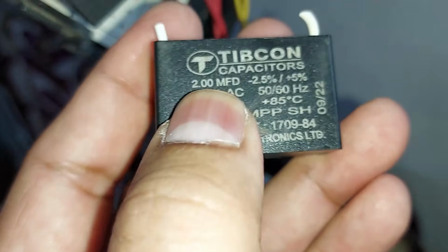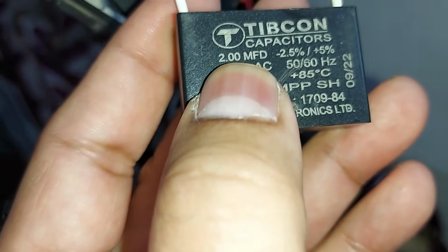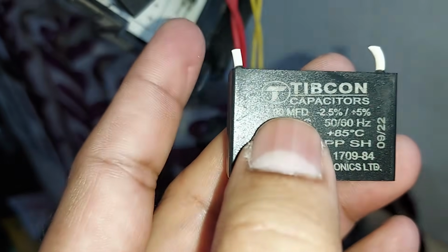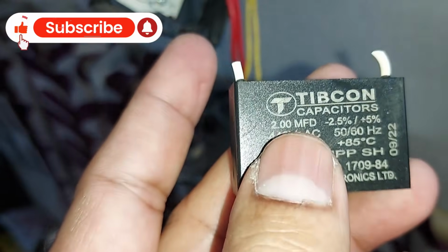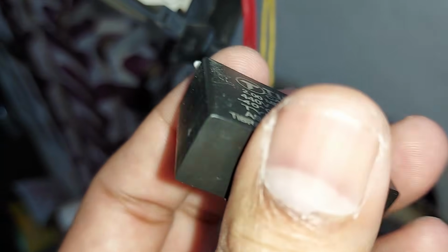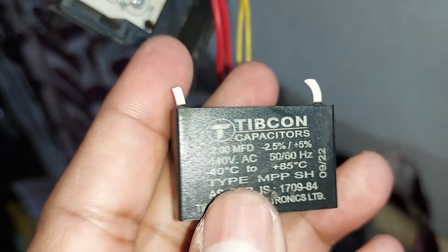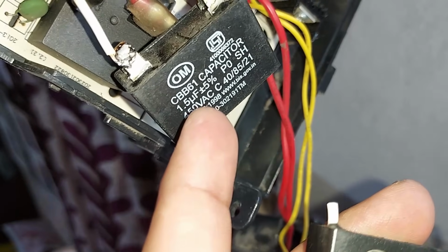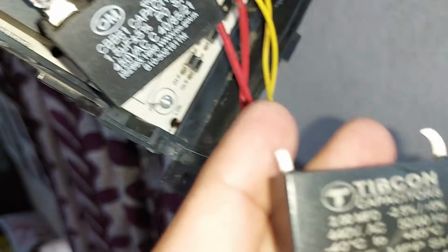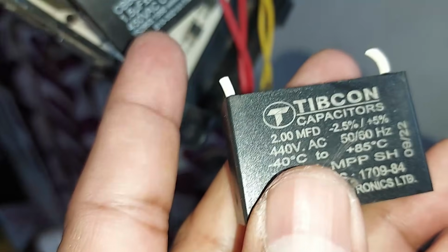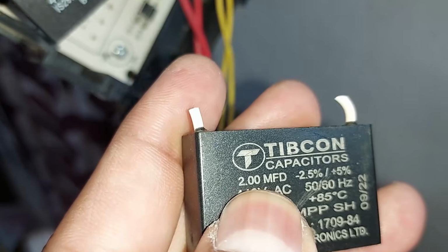But if you use more than that, like 1 MFD or more, then that's going to make trouble for the motor or the fan coils and all. Maybe it will overheat and it may burn. So always use a good capacitor with the exact capacitance, like the original one. But if you don't get the exact capacitance, you can use a little more than that. 0.5 wouldn't matter that much.